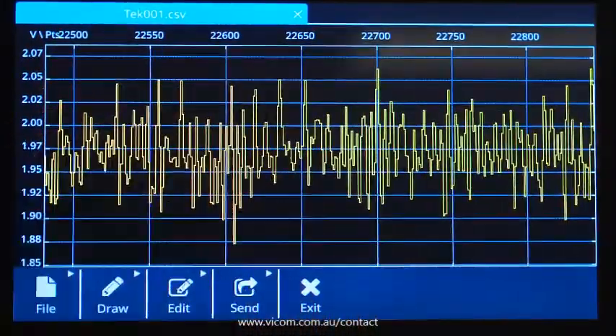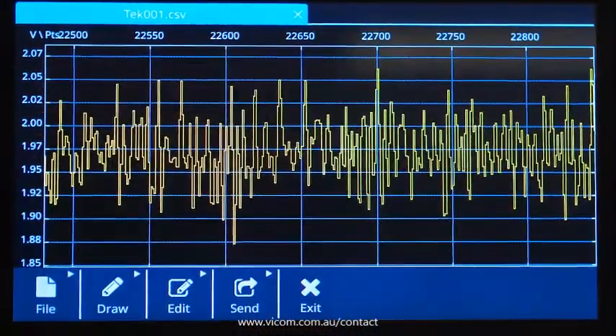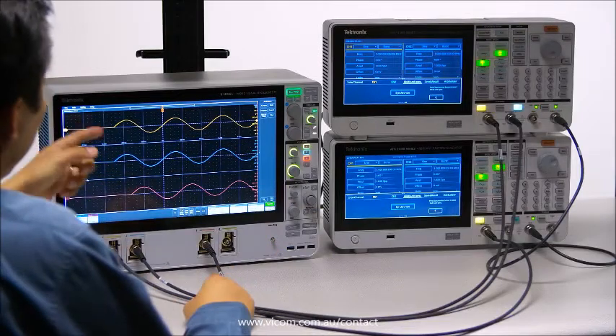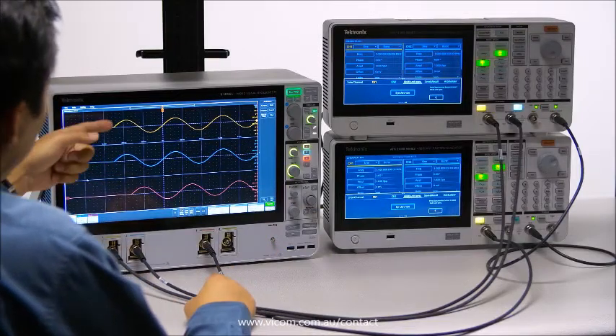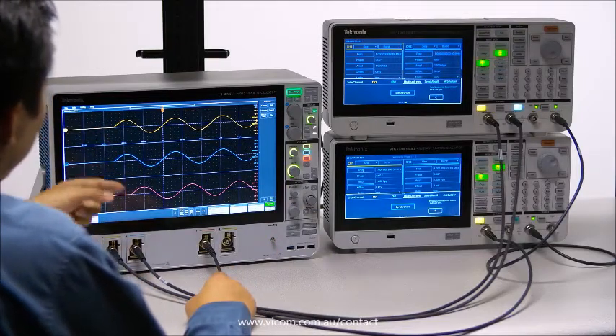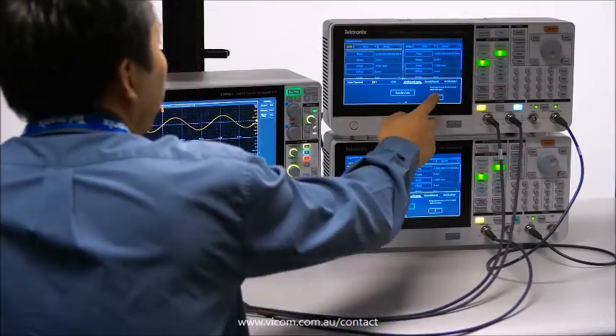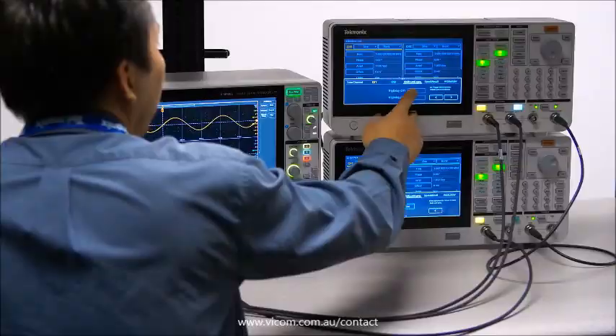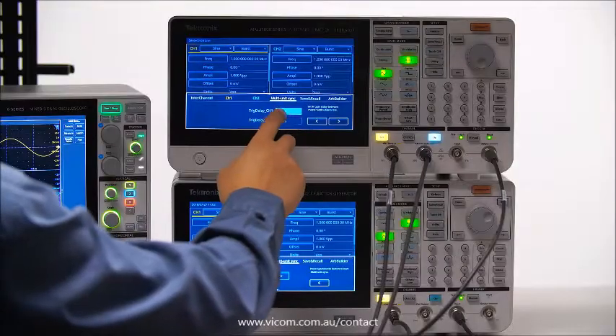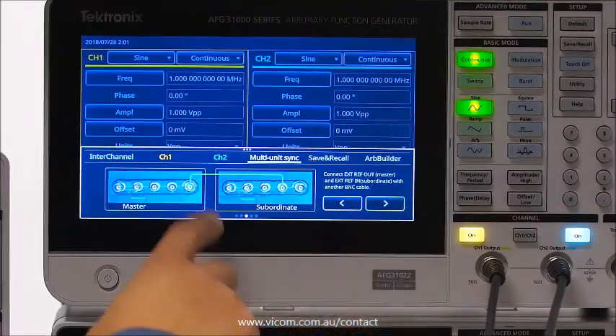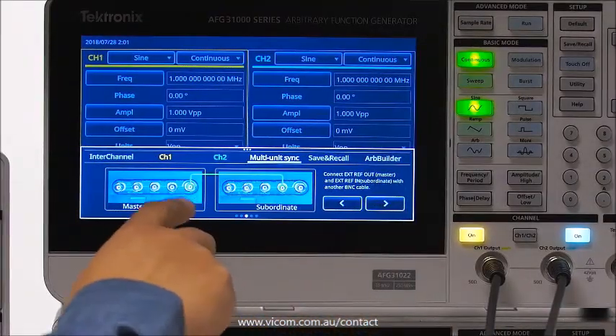If you need more than two channels of waveforms to simulate your device under test, multi-sync enables you to sync up more than one unit in under three minutes. The on-screen wizard leads you through the process of cable connections and settings.